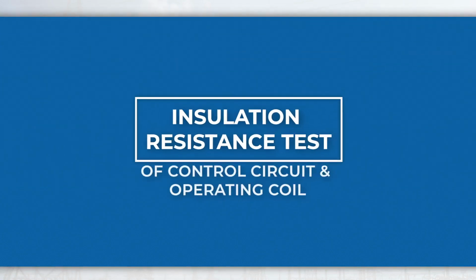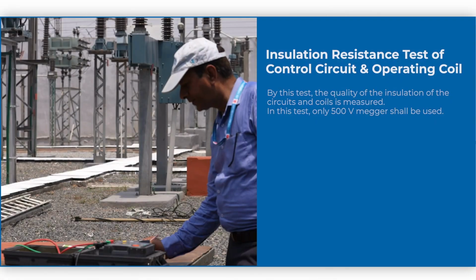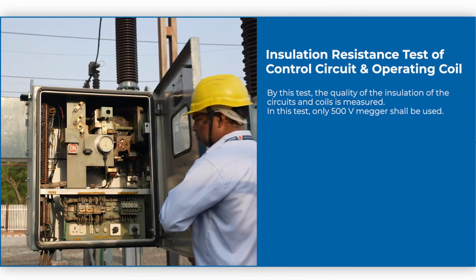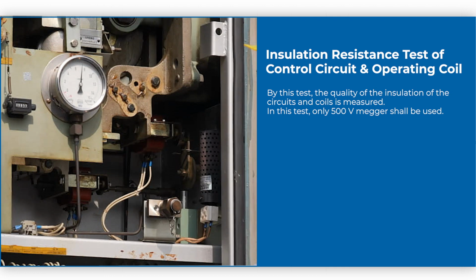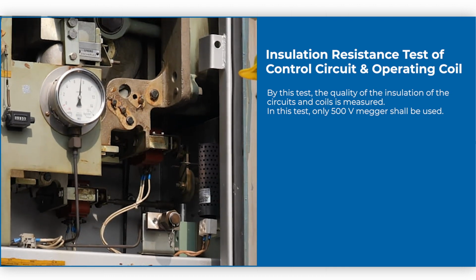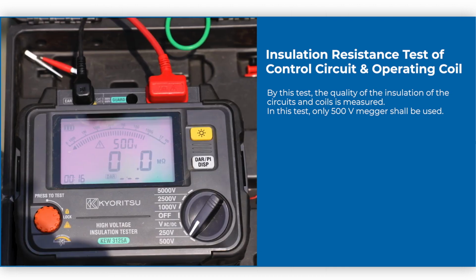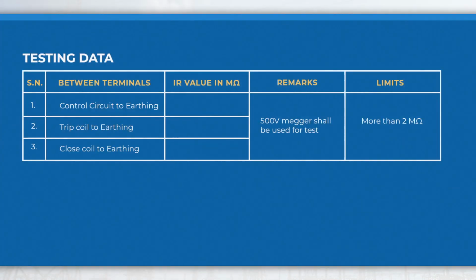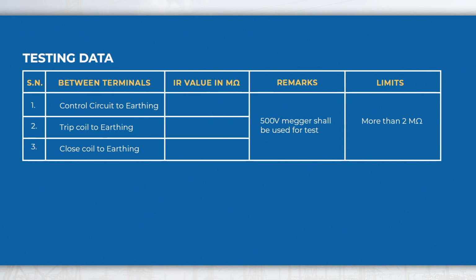Insulation resistance test of control circuit and operating coil. By this test, the quality of the insulation of the circuits and coil is measured. In this test, only a 500 volt megger shall be used. Testing data may be recorded in the format given below for evaluation and future reference.